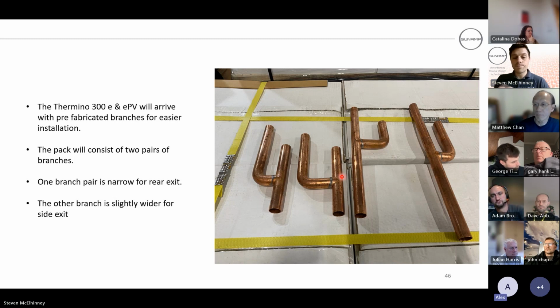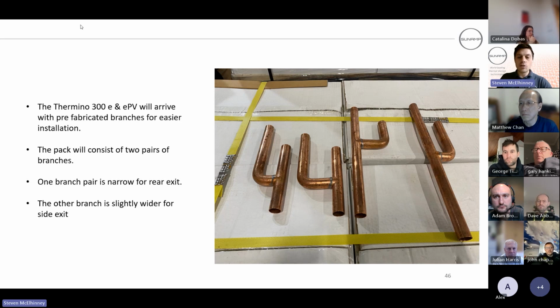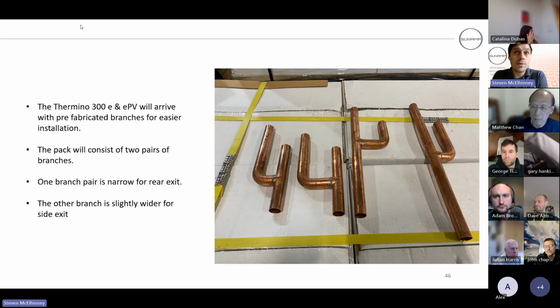And presumably you can run these as 2 separate systems as well, instead of just using the branches. Oh, so, is this a space heating question? Well, not necessarily, just for 2 supplies. We wouldn't recommend it, Alex. In theory you could, but you wouldn't have to with a 300. The 300 should be able to provide for 2 different outlet points if on at the same time. Your flow rate is going to be reduced to about 12.5 litres, depending on pipe runs and stuff.